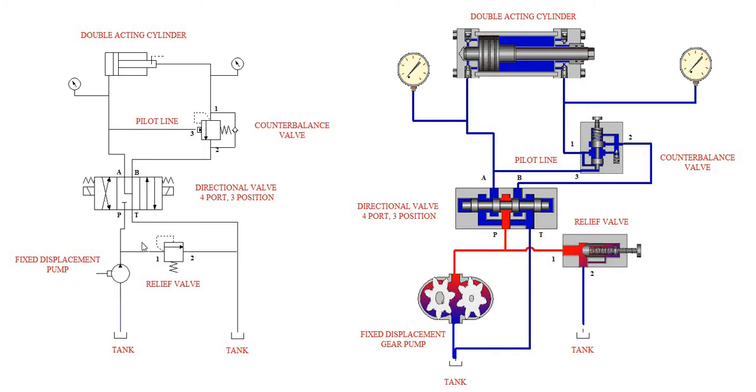The second component is a relief valve, a common component used in hydraulic circuits to control and limit pressures. The way it works is when the pressure from the pump comes, and if there's no path of resistance lower than the setting of this relief valve, this upstream pressure at 1 will move, so envision this arrow shifting over to allow flow to go from 1 to 2 into tank.